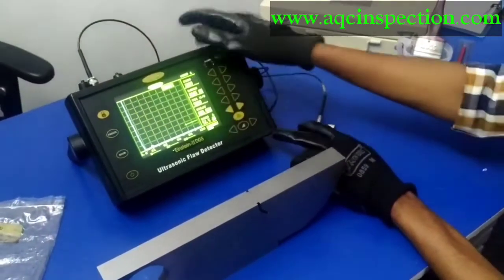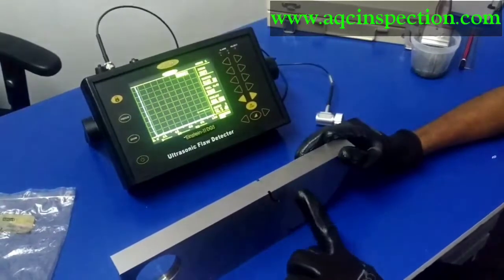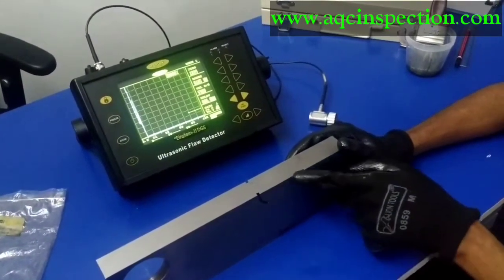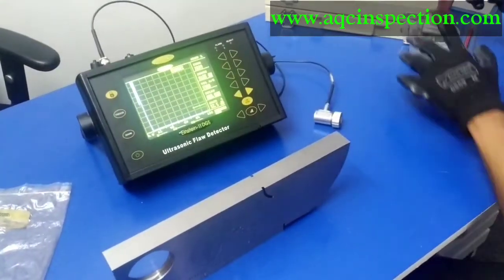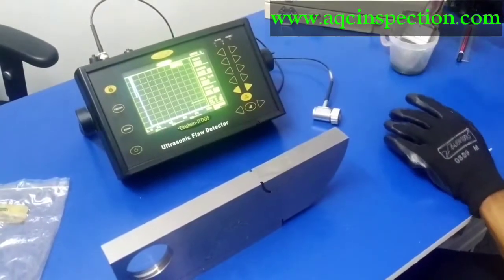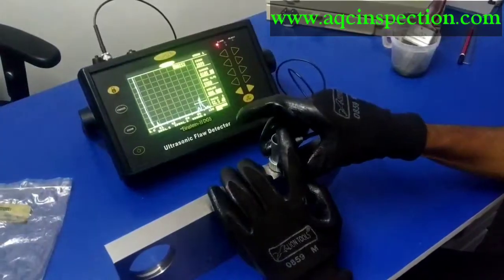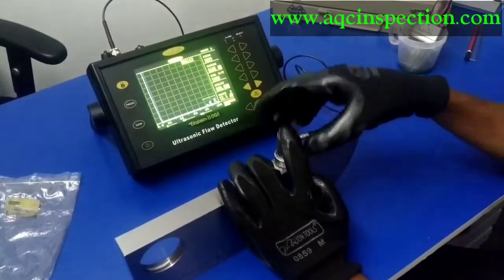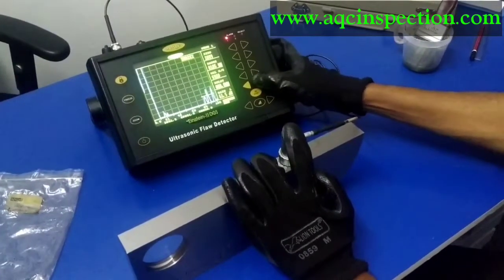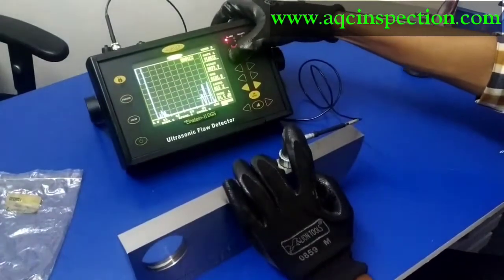Which will be somewhere under here. As you can see, it is 84. This value right here, this dimension is 85 mm and this one is 95, 91 and this last one is 100 mm. So I am going to apply a little more couplant here. Place the transducer right on top. As you can see, I am getting three echoes in my CRT screen. So I am going to increase my amplitude a little bit. And I am going to adjust my gate.